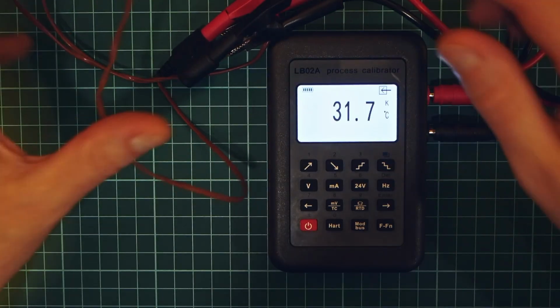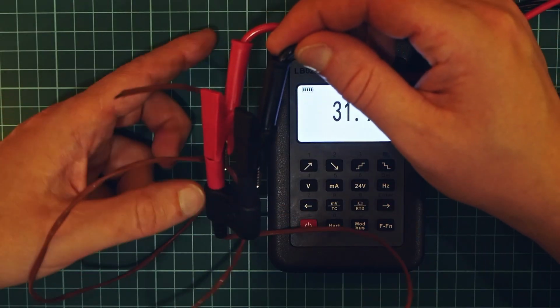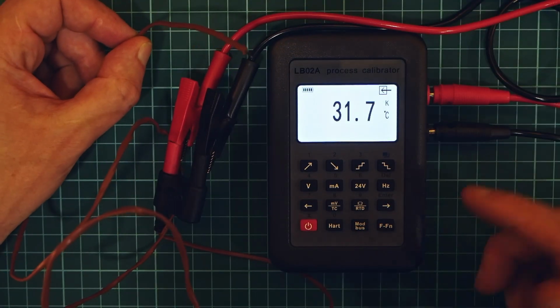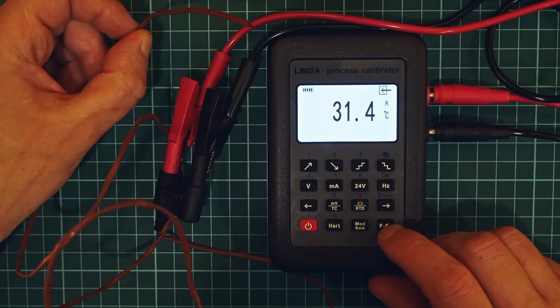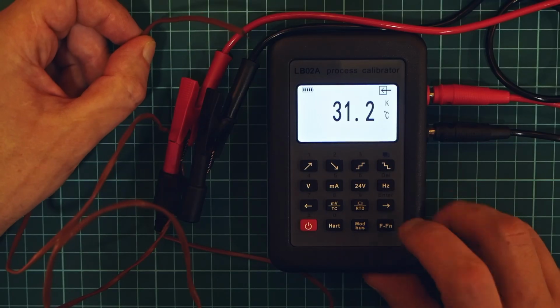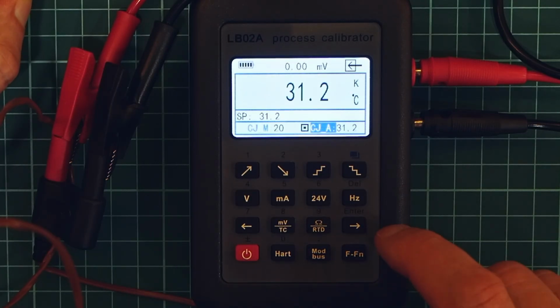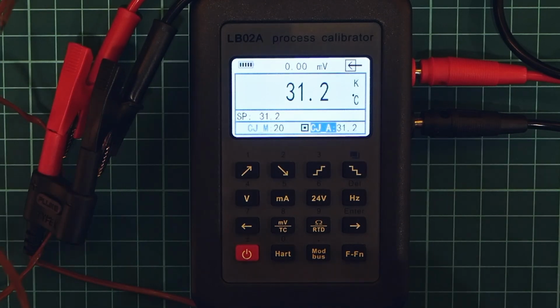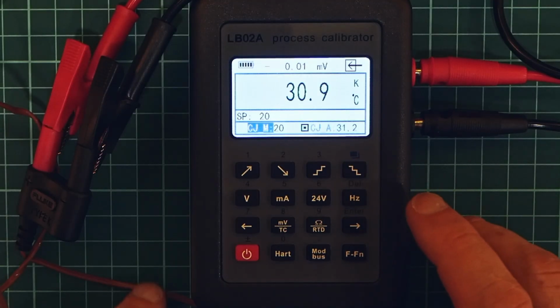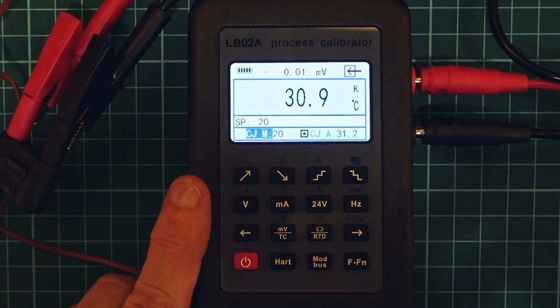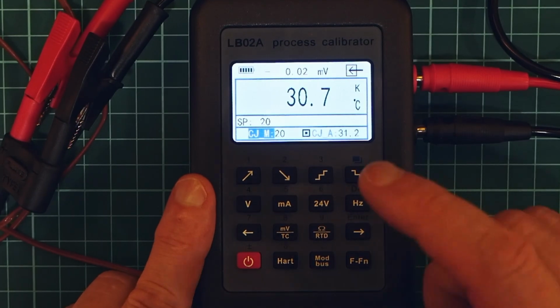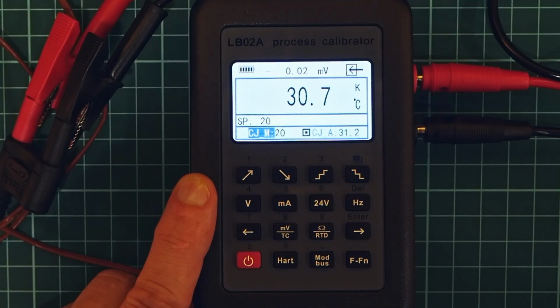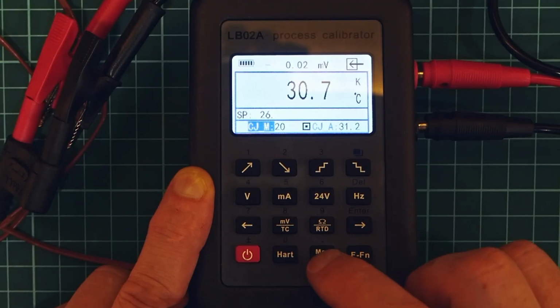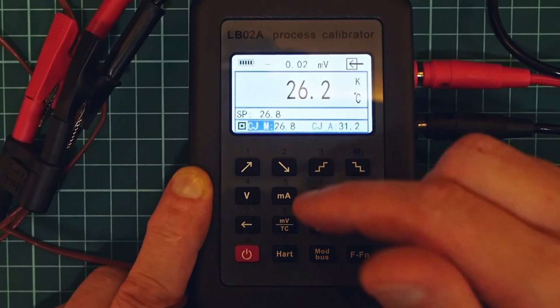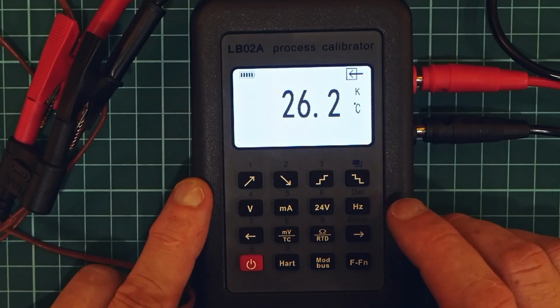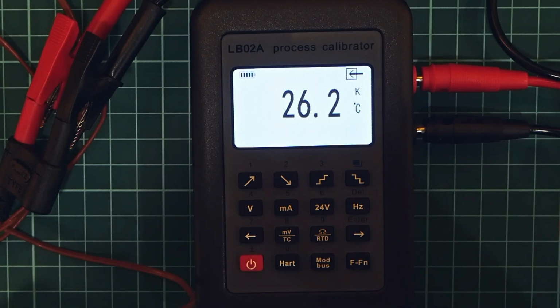But you know, it shows too much. Why is it doing this? It doesn't show correctly, right? This is because you need to enter the cold junction value here. So you press function, and this is right now set to automatic cold junction. So we need to go to CJ M, manual cold junction, and enter what we measured with that Fluke multimeter, 26.8. We enter it, so this is the reference point. So right now the value is more or less the same, yes?